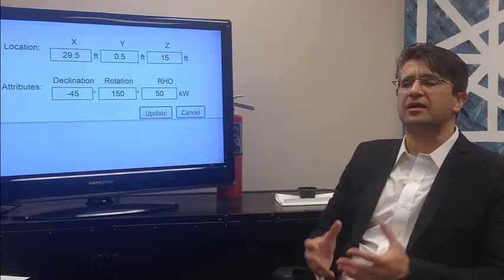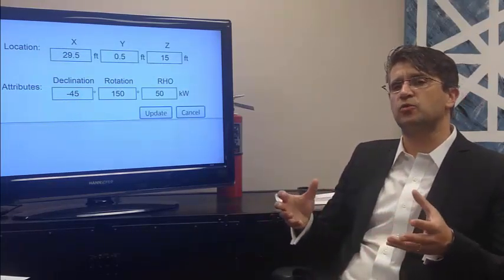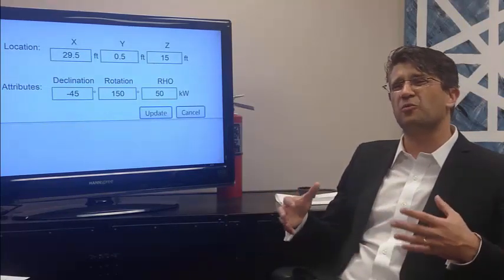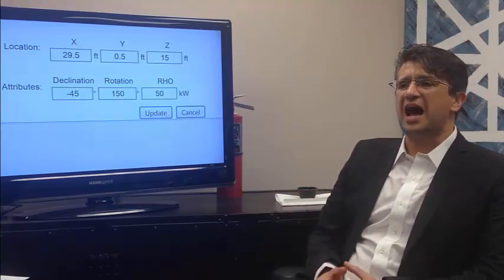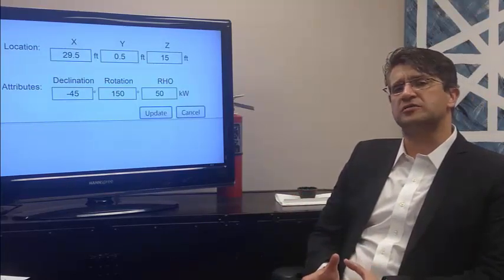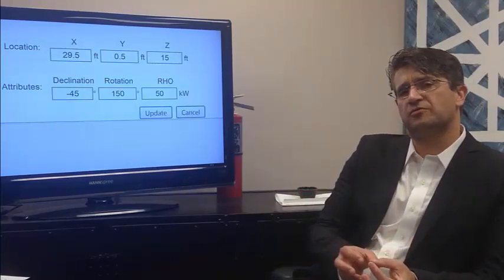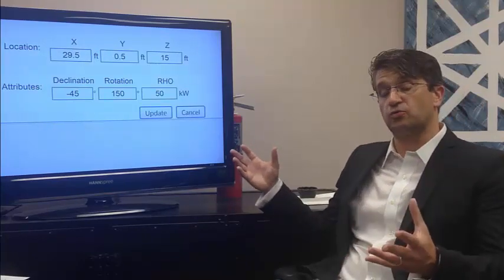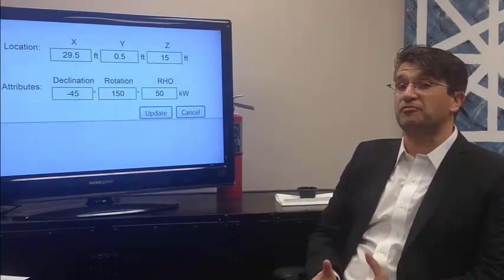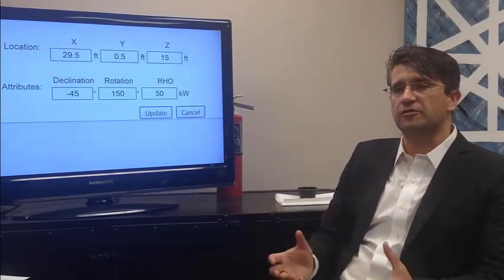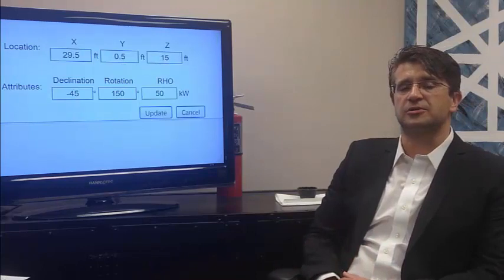And that will allow me to use less equipment and cover a larger area without really impacting the risk that greatly. So not all zones are the same. Sometimes you want to detect a smaller fire. Sometimes it's okay to wait until the fire has gotten a little bit larger before you detect it. And that's going to have a profound impact on the coverage and the number of detectors that you're going to need.